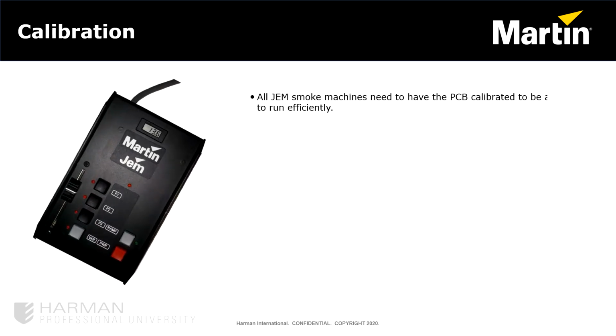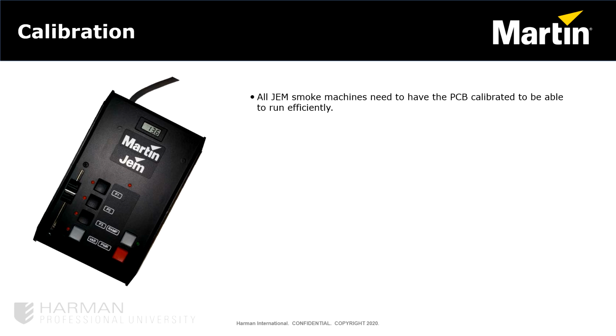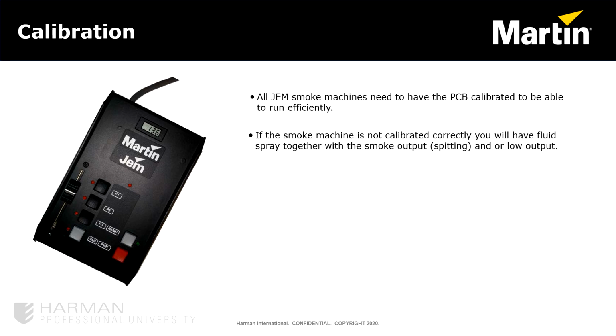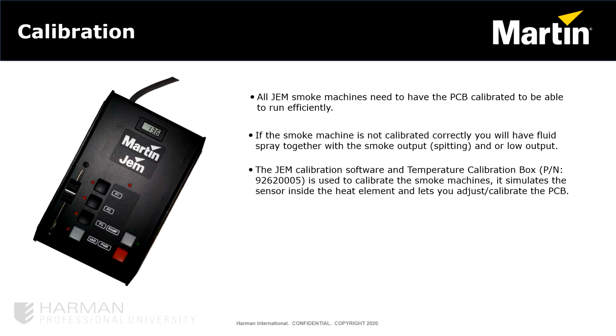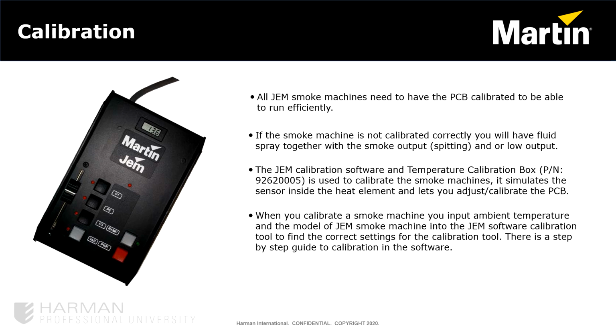The calibration tool mimics a heater, so a millivolt reading can be sent back to the PCB, emulating the temperature rise of a heater. The calibration tool can be used for two purposes. The first is the calibration as it was designed for. The second is to use it as a mock heater. If you want to test for the pump's correct operation, slave the calibration box over the thermocouples and send the millivolt reading so the machine goes ready. You can then fire the machine and verify the pump is working correctly.